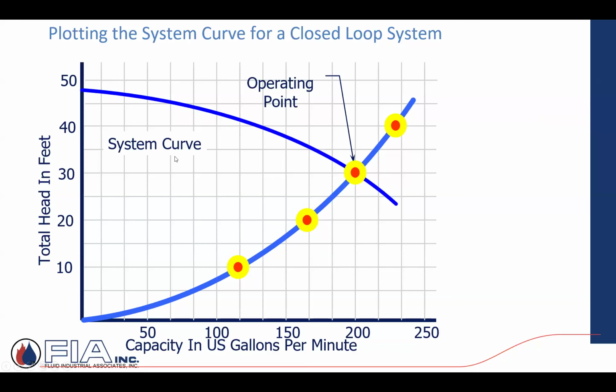And the reason for that is this. The system curve is always going to intersect the pump curve. The ideal setting is to buy, select, and put in a pump that meets your design criteria. A lot of times that doesn't happen exactly, and you can calculate, or the software nowadays will calculate, where that pump is actually operating. But there's this squared relationship. It's maybe a little confusing at first, but all it's saying is once I know a given set of conditions, in this case 200 GPM, 30 feet of head, I know what that system curve is going to look like. Years and years ago, they would sit down and mathematically do what we just talked about. Today, you plug it into software, it spits it right out, tells you exactly what the curve is and where it's going to intersect. Yes, sir.